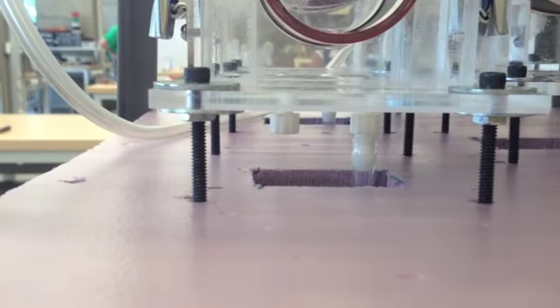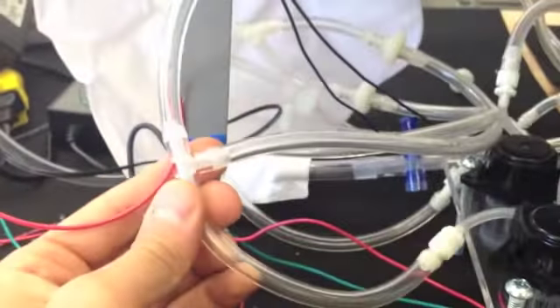So then for the bottom half of it, it's kind of messy down here. Obviously, this whole pile of electronics will be neater in the actual box, but right now it's just sprawled out on the table. From the bottom, that connector does the venting, the pressurizing, and the draining. The same tube comes down here and gets split into a tree. One end goes into the pump, which we'll get to in a second, and the other end comes over here, which networks together with all the other ones, and check valves stop them from interacting with each other. And then they come into this solenoid that's taped on the wall here.